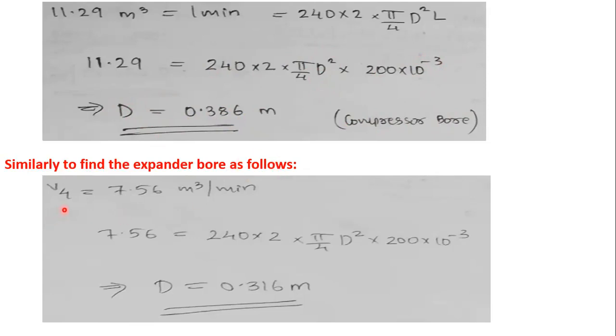Similarly, for the expander: V4 = 7.56 m³/min = 240 × 2 × (π/4) × D² × L. Solving gives D ≈ 0.316 m, or 316 mm for the expander bore.